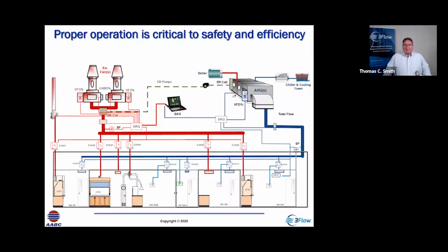We can add our building automation system, which is an array of sensors and controllers and actuators. All of these parts and pieces have to function properly and be working in tandem in order for us to deliver the appropriate amount of flow and exhaust it from these spaces. And then we can add additional systems now, occupancy sensing and demand control ventilation. These systems add additional complexities that have to be confirmed that they're operating properly so that we achieve the objectives. And then we add the most difficult component, which is the humans. The people can do some crazy stuff in the labs, and they're very innovative people. And so we're constantly trying to make sure that we're meeting their needs, which we call the demand for ventilation.